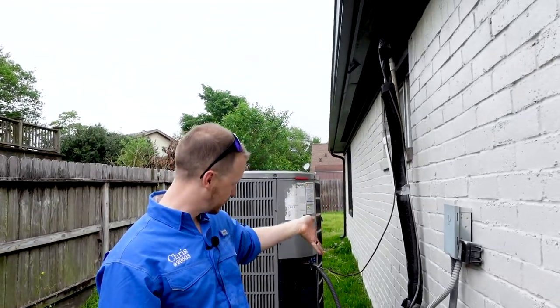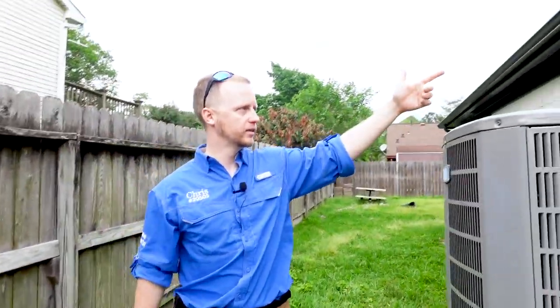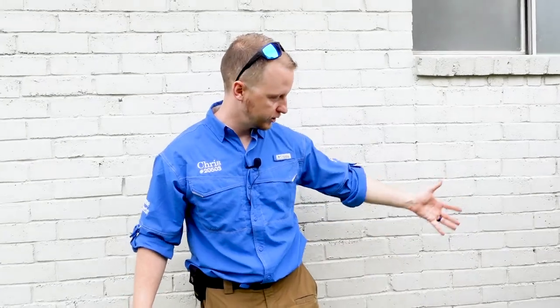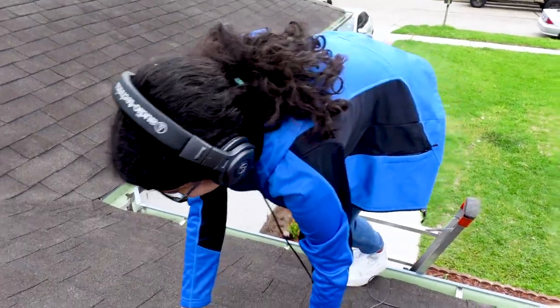There's a giant hole with water coming out of the AC unit — another good HVAC find. That's the secondary drain, but James also said the primary is leaking into the attic as well. This area doesn't help the foundation. Excessive moisture invites termites, and you always want to terminate your condensation water away from the structure.